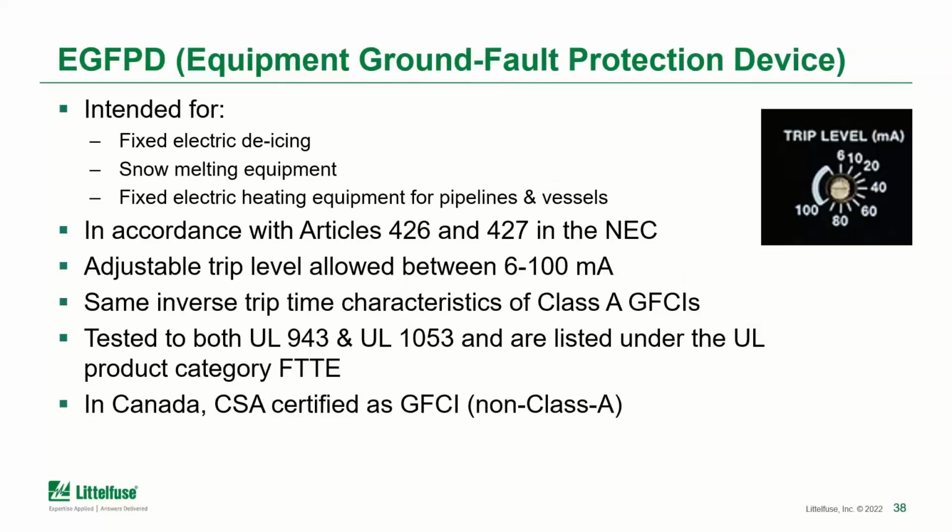I mentioned EGFPD early on in the presentation. Now, this is a specific type of device for protection of equipment, but it does have sensitive trip levels. And there's some specific applications for it in the NEC related to de-icing and snow melting equipment. And they do have adjustable trip levels. They have to follow that same UL trip curve, so they are sensitive trip levels, but they are adjustable, and so therefore are not GFCIs.